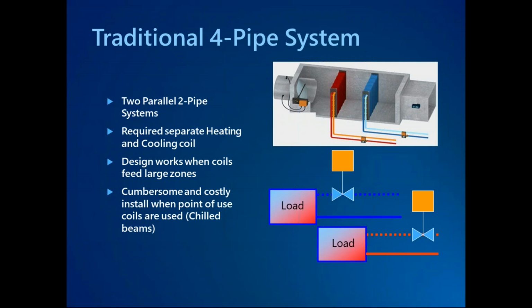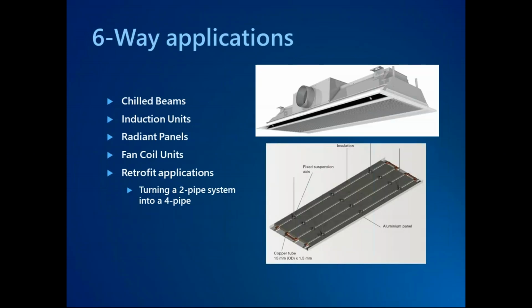Now these four-pipe systems were great when we were able to put the coils in the airstream, feeding a large zone, a large area with multiple diffusers, maybe a handful of rooms or a couple of classrooms, things like that. With the advent and introduction of chilled beams, which we like to call point of use coils, they effectively take the place of the diffusers. It is not economically viable to run these four-pipe systems to every single chilled beam throughout the building. So the goal was to come up with a better solution.